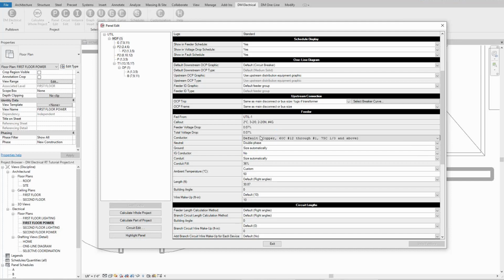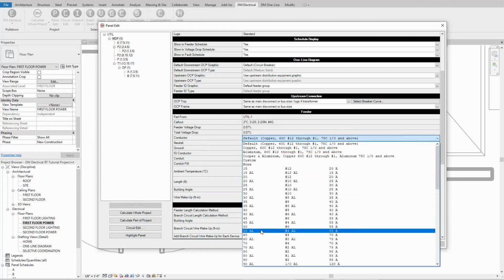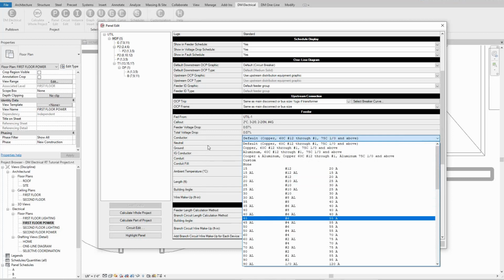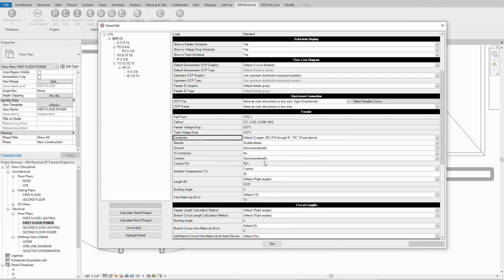To do all of this, you would have to manually set the wire size, which worked. But again, if something changed, you had to remember to also change the wire size to account for it. So now it's sizing automatically based upon these settings, which is more convenient for you. It's also much better documentation so that when someone else picks up the project, they're not wondering why you've locked this wire size. They know that, oh, you're sizing this based upon a double neutral, or you're sizing it based on a higher ambient temperature. So your design intent is actually more clear with these additional options as well, which is helpful for other engineers or you when you come back to a project after it's been put on hold for 6 months and can't remember what you were doing.